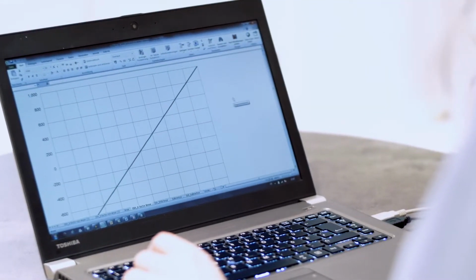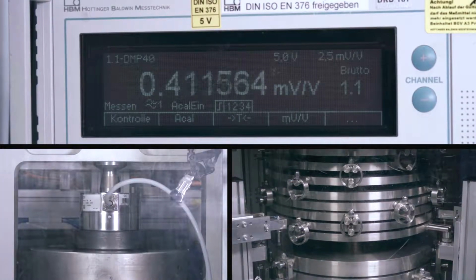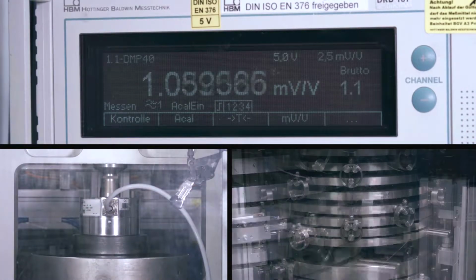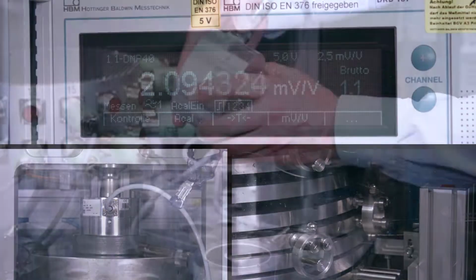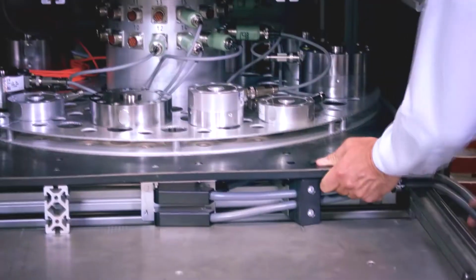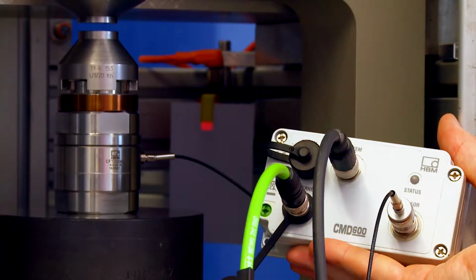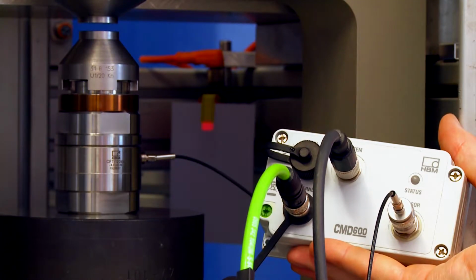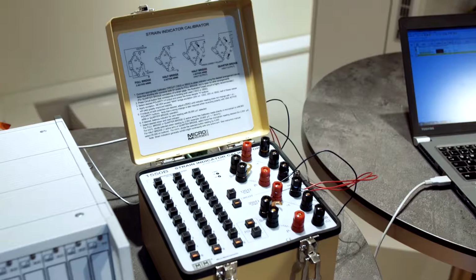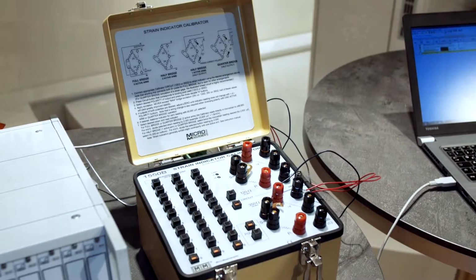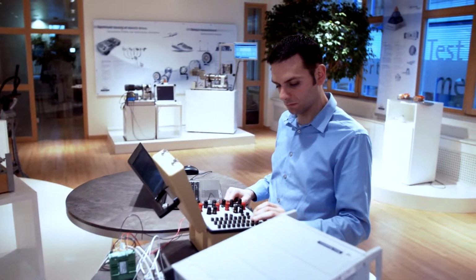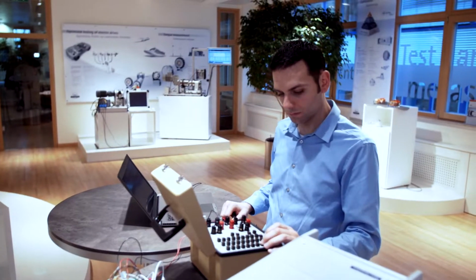Every measurement chain should ideally be calibrated. With a complete measuring chain using, for example, force transducers, traceable calibration is possible, while with a complete measuring chain using single strain gauges, this cannot be done, since it is impossible to apply traceable strains. When calibration units are used, however, there may be apparent deviations of the test result, in particular when the calibration unit ignores the nonlinearity of the gauge factor.